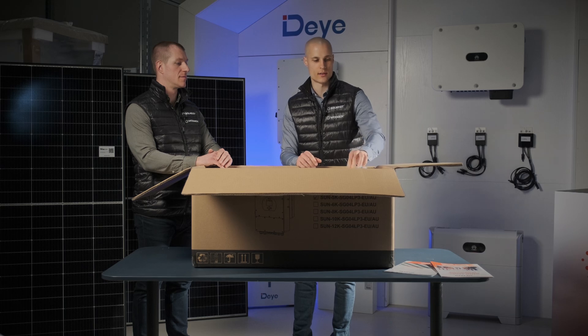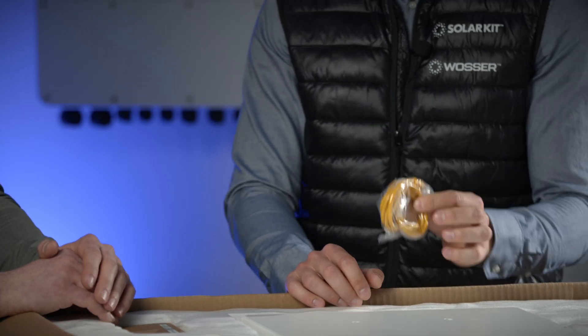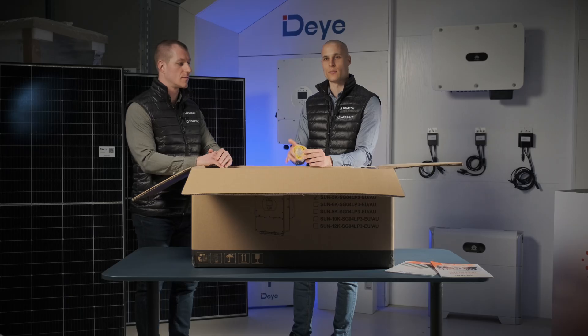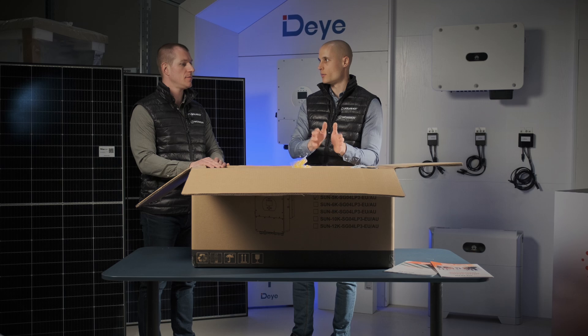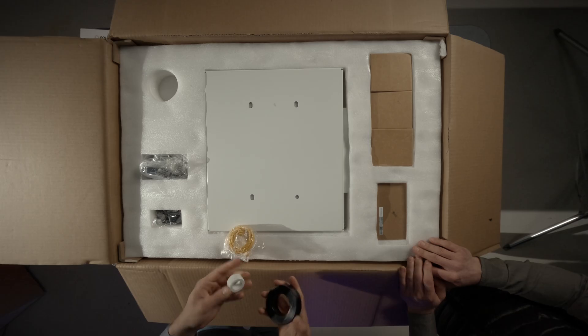The package also includes the factory MC4 connectors along with all the necessary screws, plugs, and cables needed for parallel communication. Here's a small yellow cable that we use when connecting multiple inverters, and this orange cable is used to link them together. This is a common issue: people buy two inverters, try to connect them in cascade, and while they may physically connect them, the system doesn't work as expected. The key point is that Deye inverters can only be connected in parallel if both inverters are using the same battery. Without a shared battery, they cannot be connected in parallel — the battery is absolutely essential for this configuration.